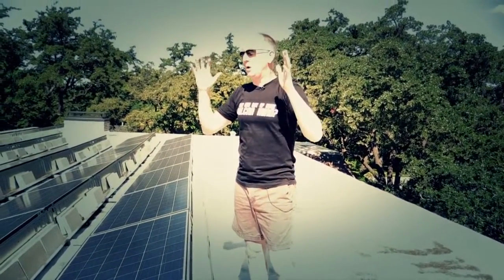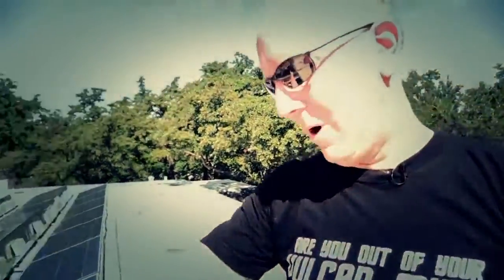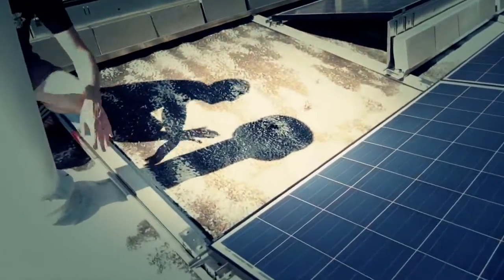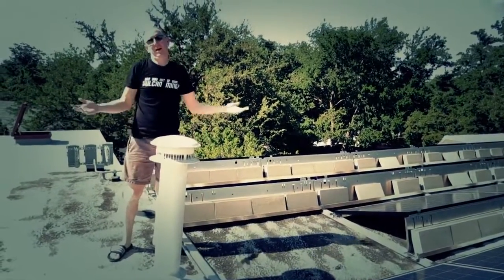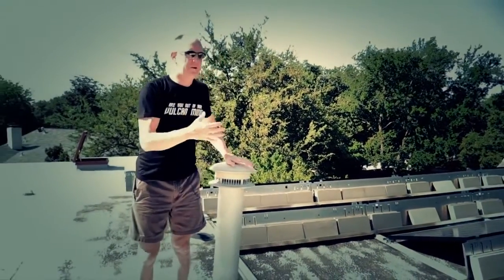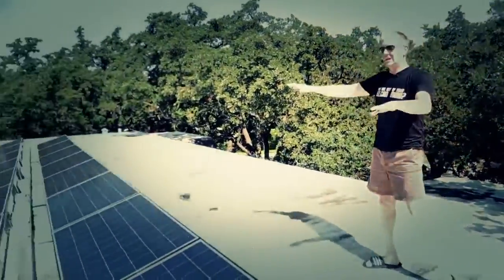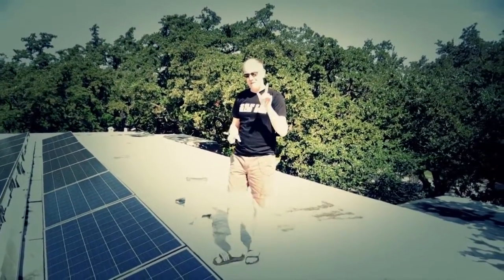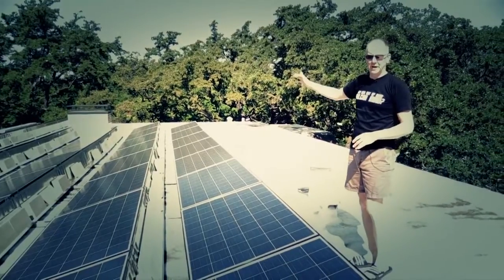When we were looking at the roof, they laid everything out to figure out how many panels we could fit. You'll notice there's a gap — the reason is simple: it's the shadow from this exhaust tube. That one little shadow prevents putting a solar panel there. I was surprised how big a difference just a little bit of shade can make on system performance. This roof was perfect for a solar array because it's completely flat, and the trees around the edges are far enough back that there's never any shadow — the only shade we get is from these tubes and from the chimney.